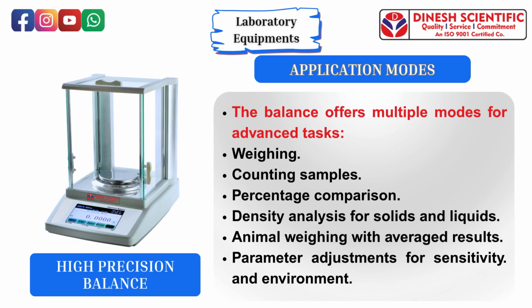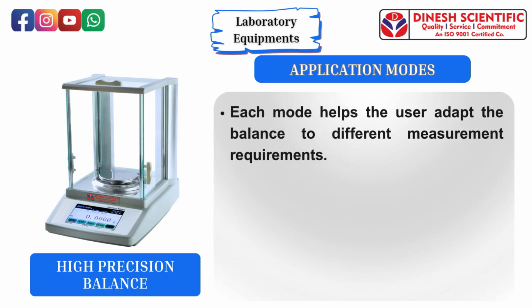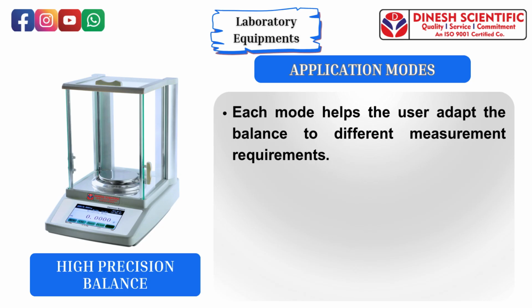Application modes. The balance offers multiple modes for advanced tasks: weighing, counting samples, percentage comparison, density analysis for solids and liquids, animal weighing with averaged results, parameter adjustments for sensitivity, and environment. Each mode helps the user adapt the balance to different measurement requirements.